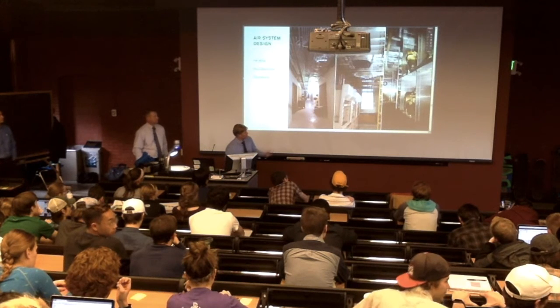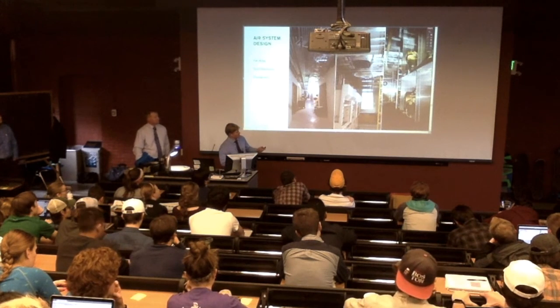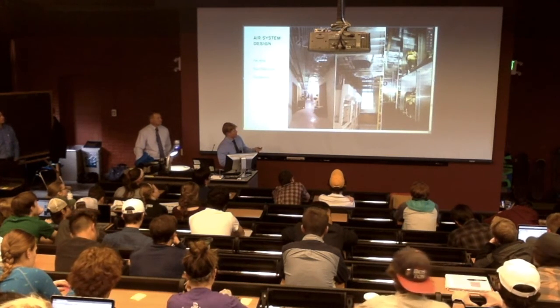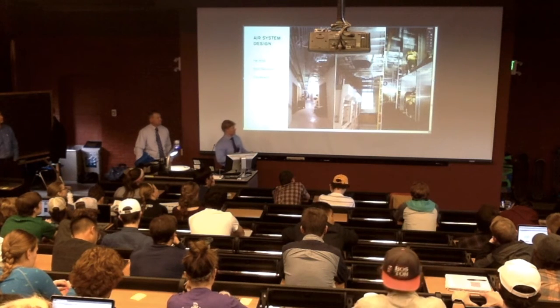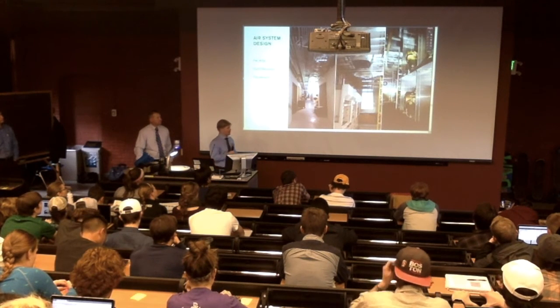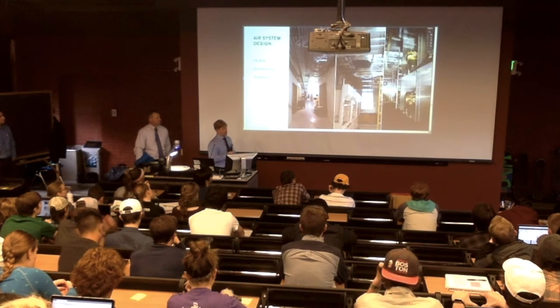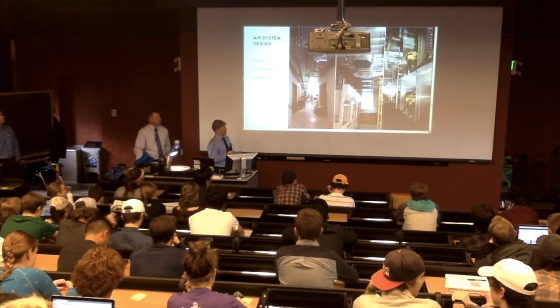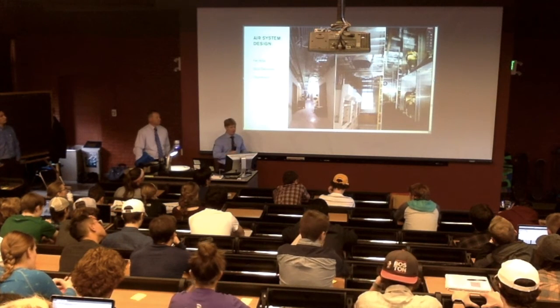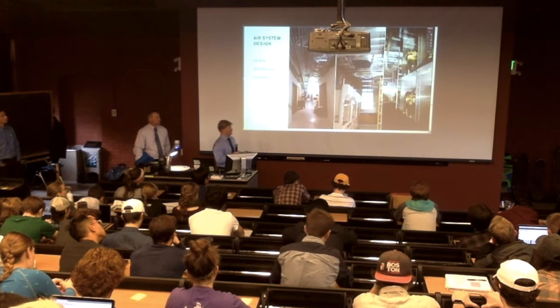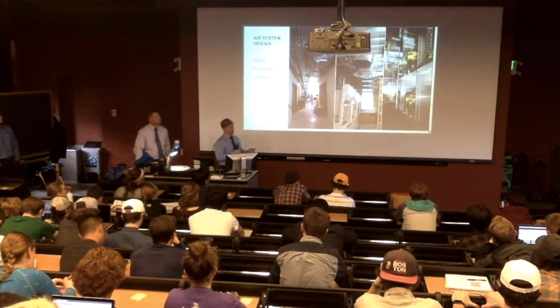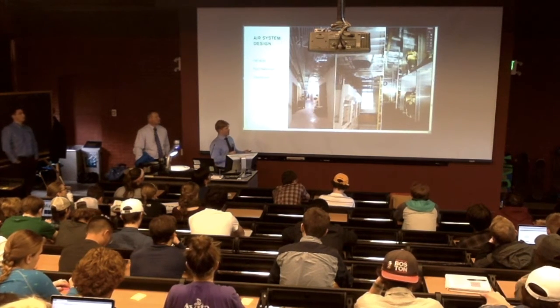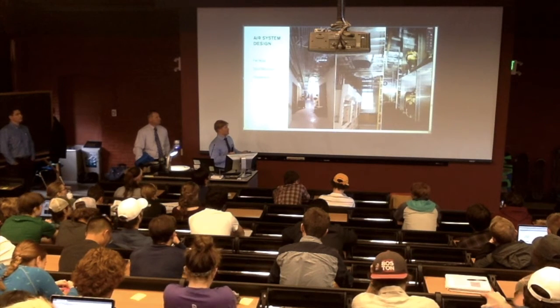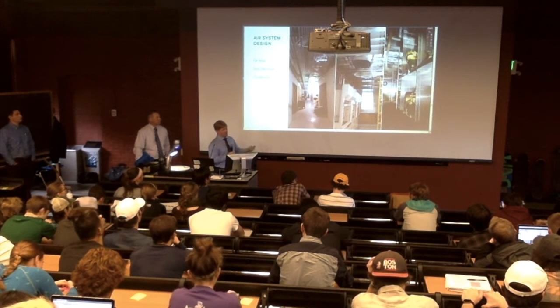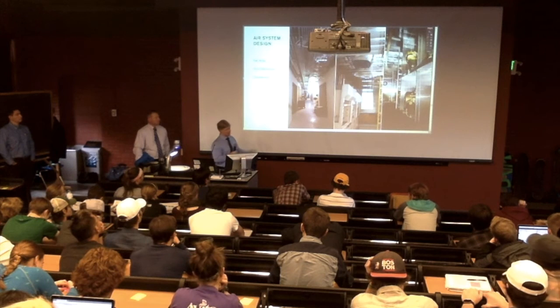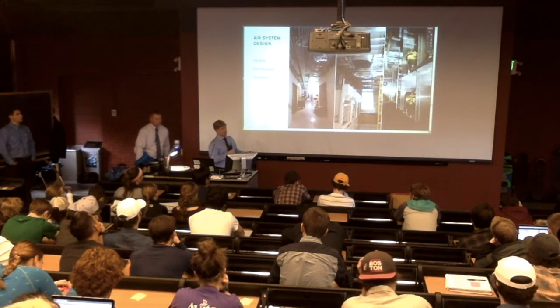Specifically inside that unit, that is what the fan array looks like. So this particular unit had, I think, 6 fans stacked on top of each other and side by side. And this is a pretty standard technology in buildings, fan array or fan wall technology, it's sometimes called. It reduces the one big fan to multiple little fans. They're easier to maintain. And if one fan goes down, you still have redundancy to run your system, especially in a lab building, where that's a serious concern.